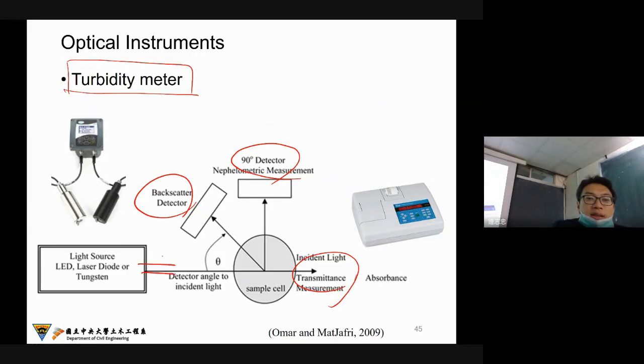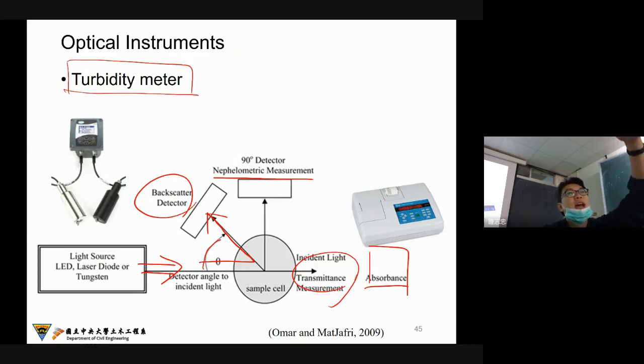Okay, so here I send a light source from the left side, and then I can get the backscatter, because this is the large-angle refraction. This is what we call backscatter. If I put the receiver at 90 degrees, this is what we call nephelometric. Hard to say. Okay, and this is the 90-degree sensor. And if I put the receiver on the opposite side, this is what we call the transmittance detector. Okay, so based on these different angles, we can get different values of the turbidity.